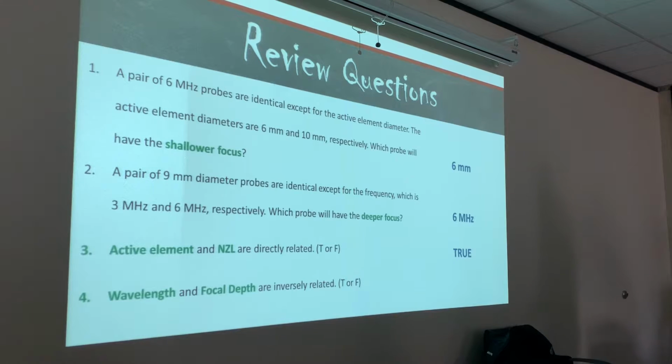So right there, you talk about the diameter, not the thickness. Absolutely, the diameter. We're talking about the diameter of the active element. Is the diameter of the near zone and the active element the same size? No. Remember, diameter is the size of the PZT element.